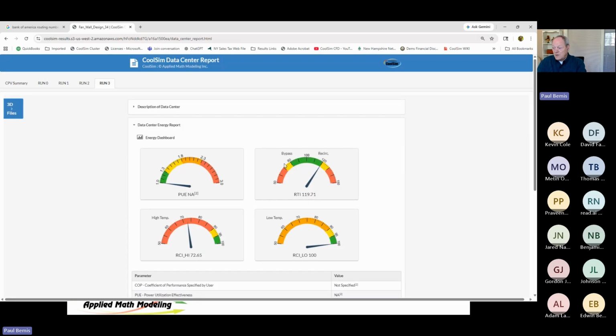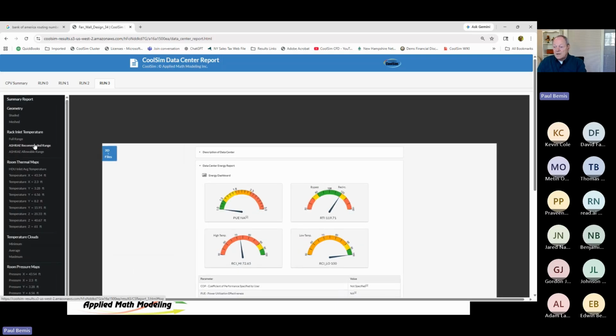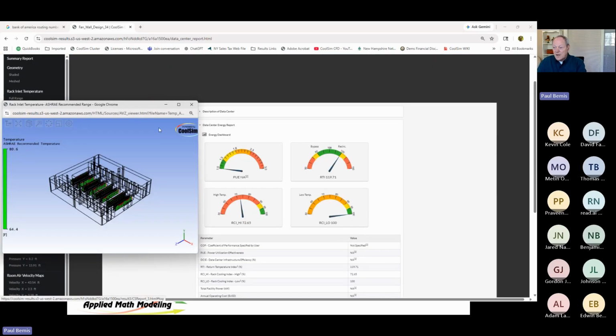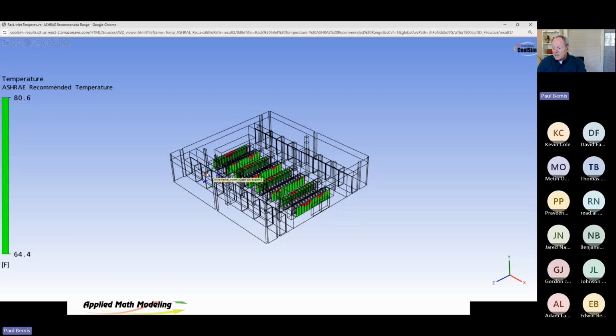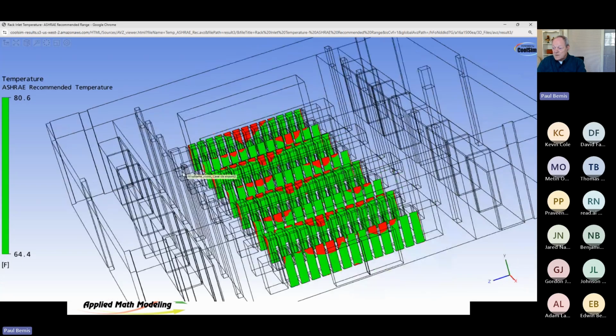So let's take a look here. I'm at 120. This one's in bad shape. You know right away at 120 that you're going to have a lot of recirculation. It's not going to go well. Look at my RCI. It's in the 70s. That's just not going to be good. So I know right away if I look at my racks, I'm going to have a lot of hot spots. Unacceptable. So here I either need to drop from 40 kW down, or I need to put more air in the room, one or the other.